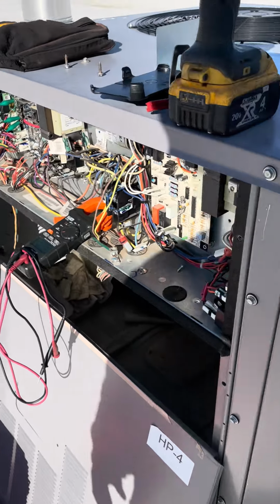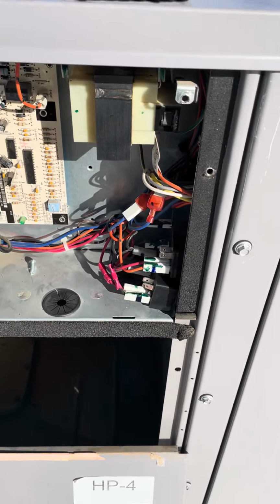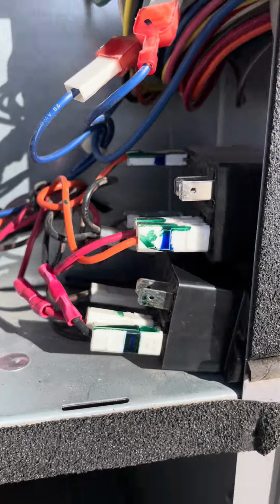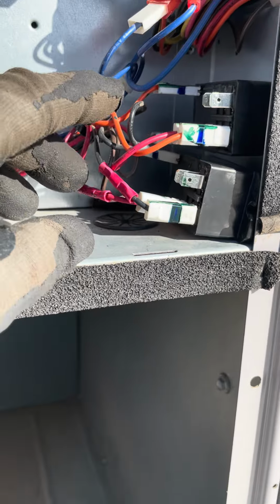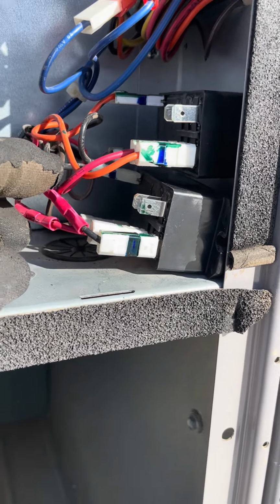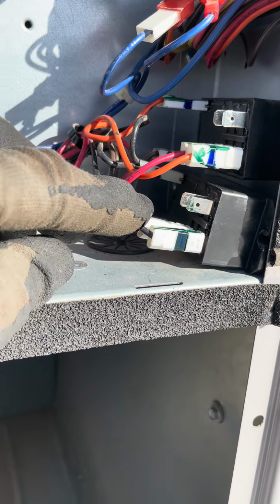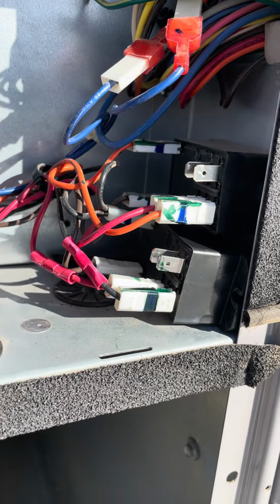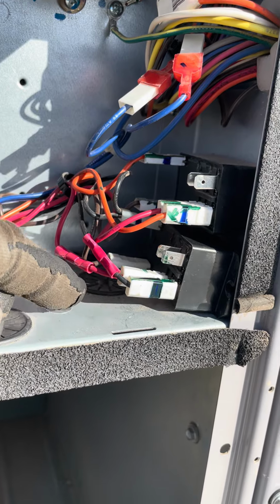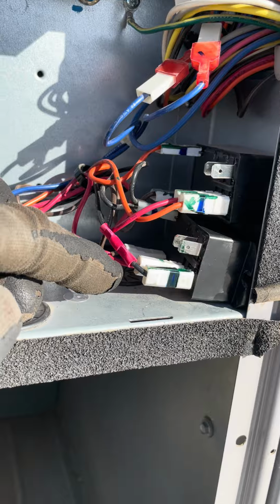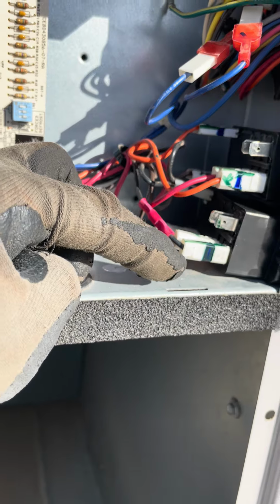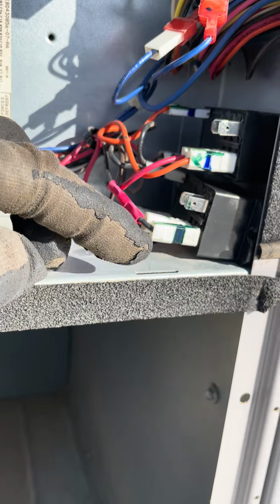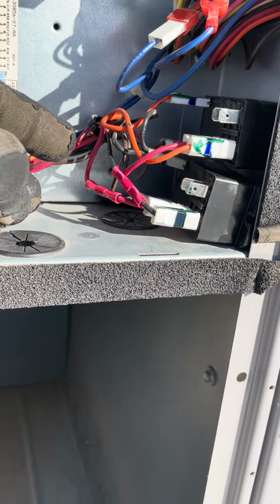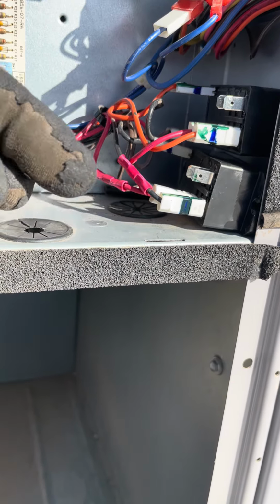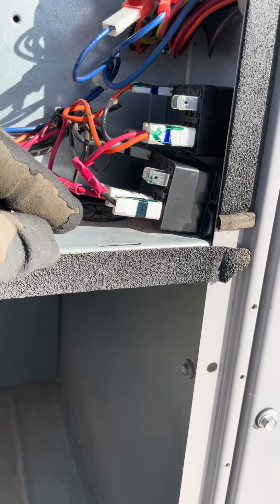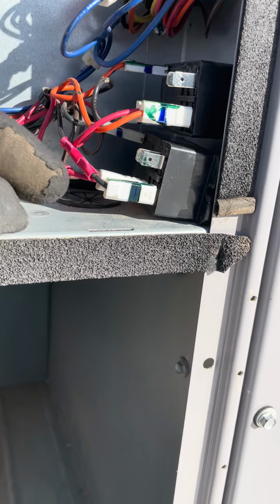So troubleshooting comes down to these two relays over here on the side. I did cut the wires and test them before, but I just put it back to simulate and let us see what's going on. So the 24 volt is controlling that side of the relay. So you have voltage in, voltage out. When the relay energizes, it'll send the voltage from the red wire to the black wire to the reversing valve to energize it. So it's not doing that right now.